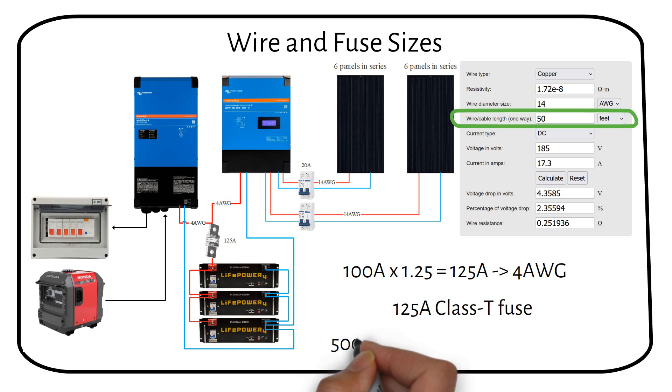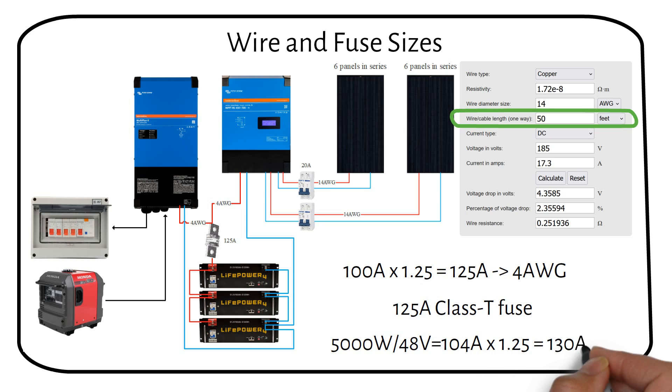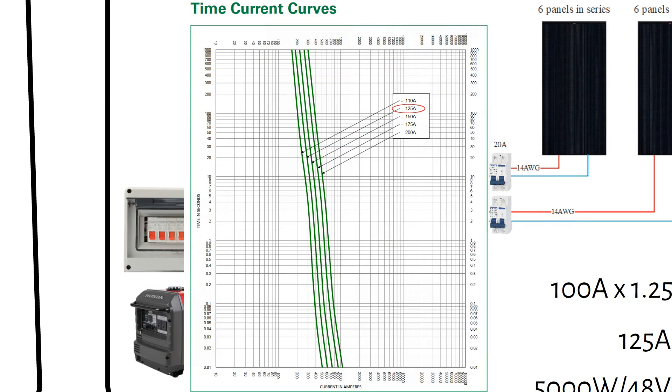The inverter will draw a maximum of 104A. Applying the 1.25 safety factor, the maximum current is 130A. Again, use a 4 gauge welding cable and a 125A fuse. While the calculated current is slightly above 125A, the fuse will not blow at 130A, as we can see in this curve of the 125A fuse.